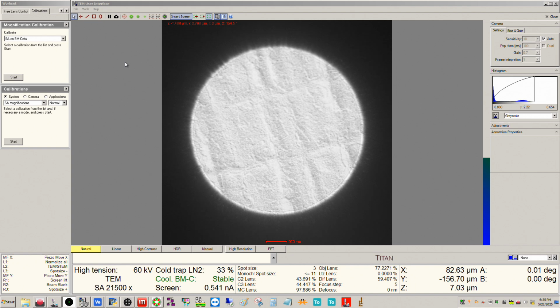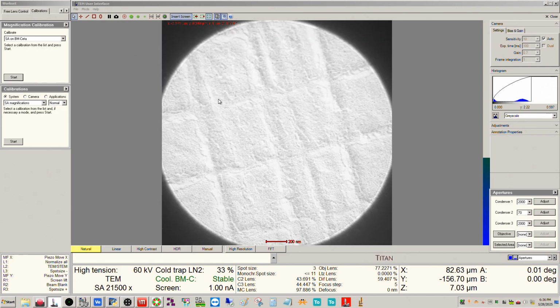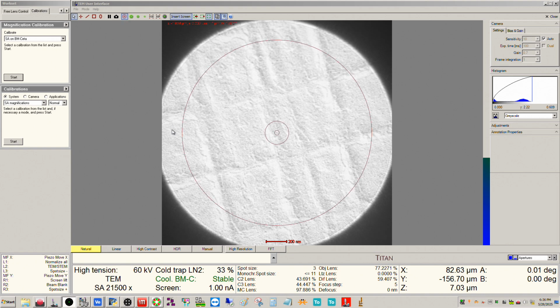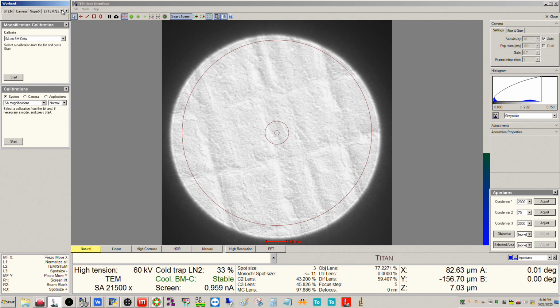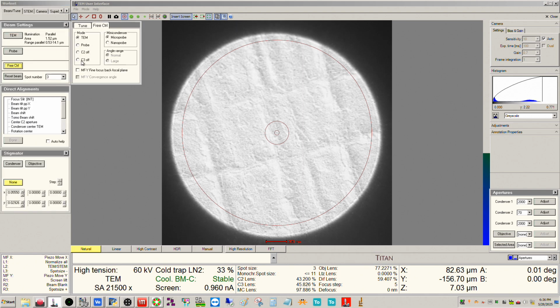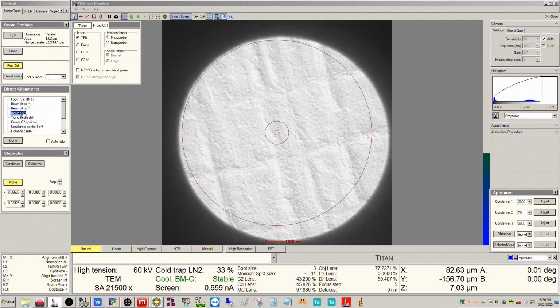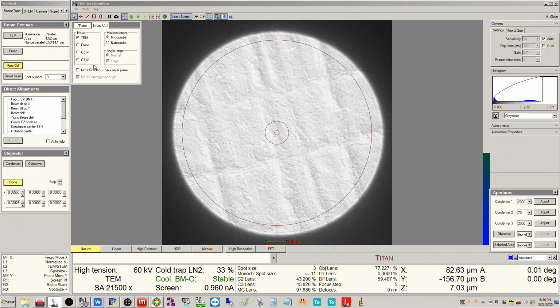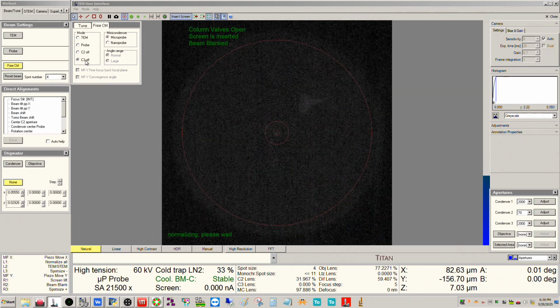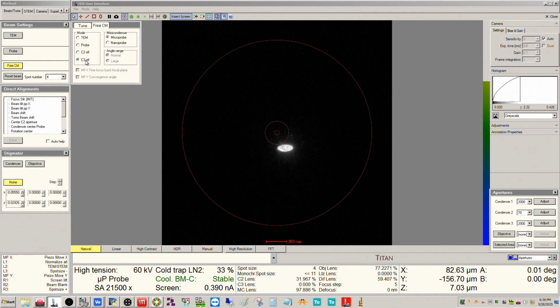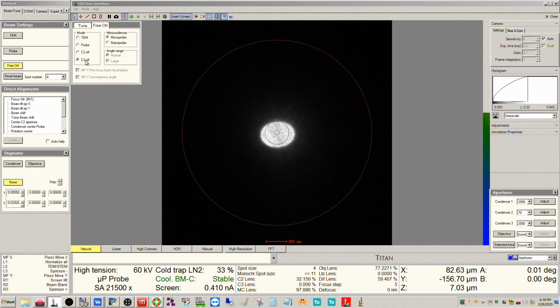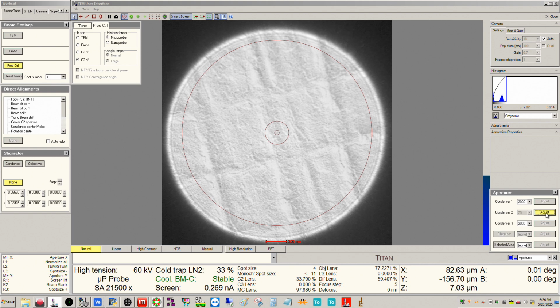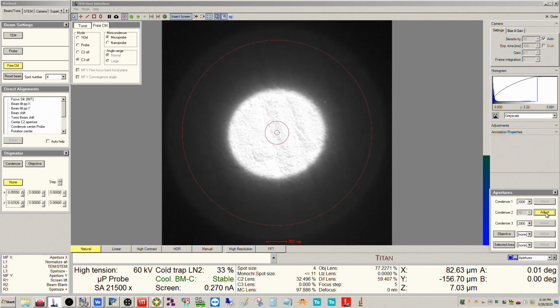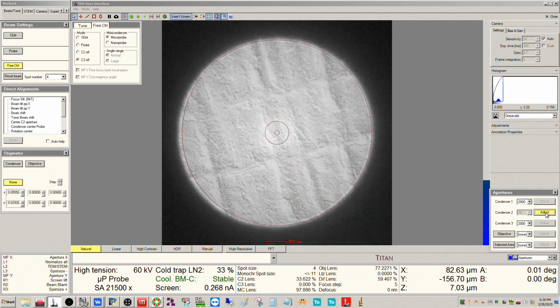So what conditions do we use here? So we still have the 50 micron aperture in. It doesn't matter which one of these you use, but I'm going to put in the 70 because it's going to make it a little easier to tune up the images that way. So let me go back here, and I'm going to check my, let me center the beam shift here. Turn off C3. Okay, that's reasonably close. All right, so I think that's not too bad.